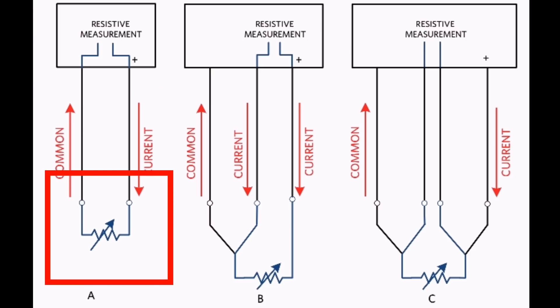Unfortunately, the copper wires of course have some resistance, and this affects the measurement accuracy. Two wire RTDs have no means of cancelling out this wire resistance and therefore are least accurate of the three types.